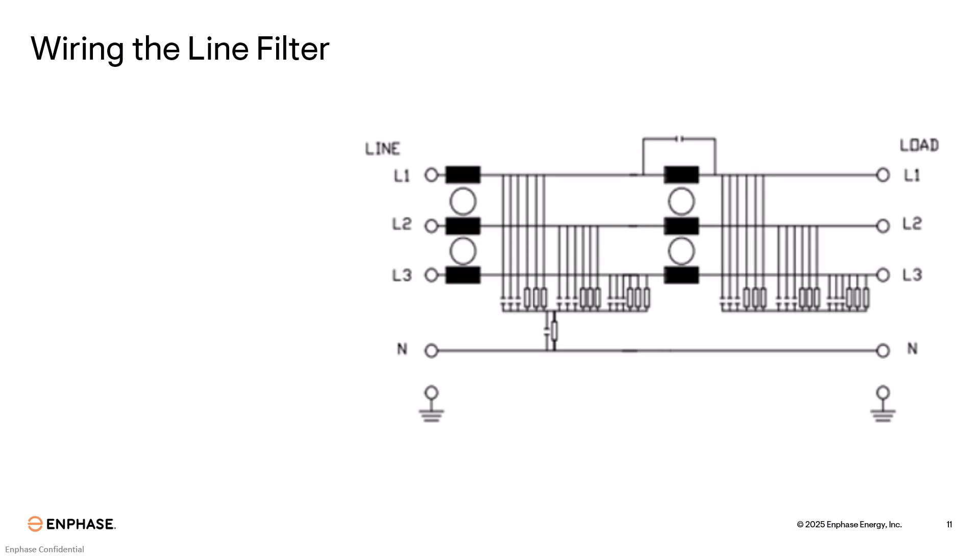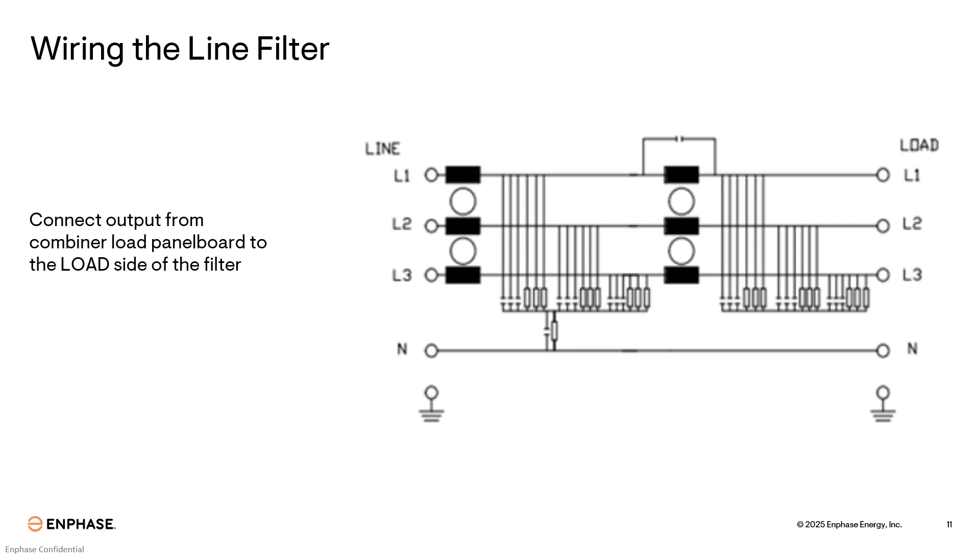Wiring the line filter is fairly simple. You will follow the labels on the line filter and connect line 1 to line 1, line 2 to line 2, and so on. The output from the combiner load panel board is to be connected to the load side of the filter. And then connect the utility feed to the line side of the filter.